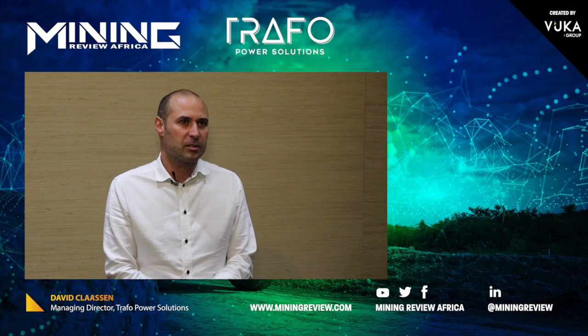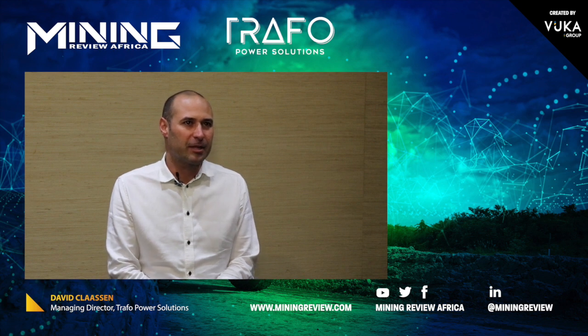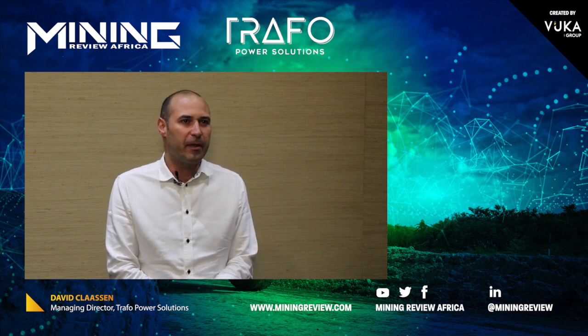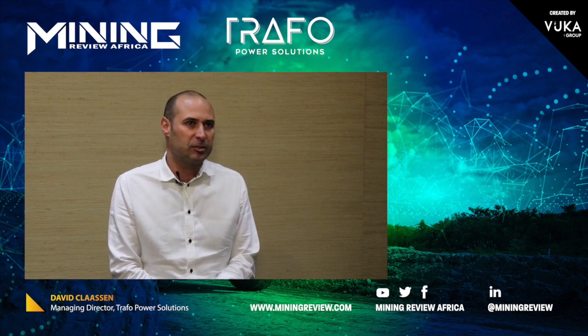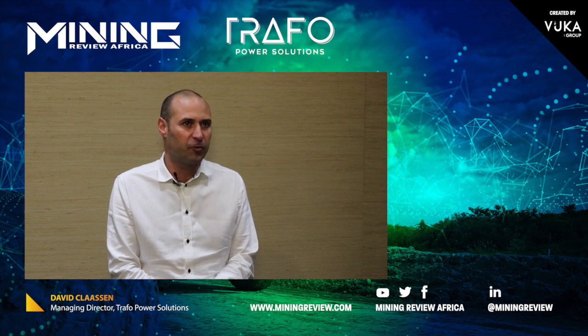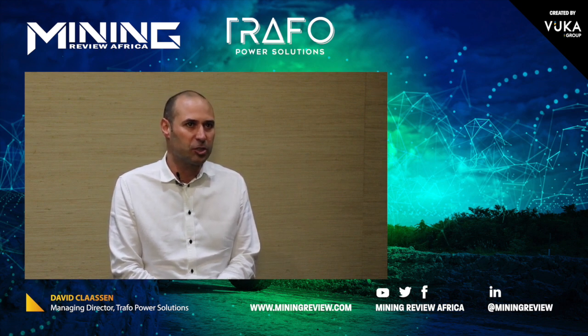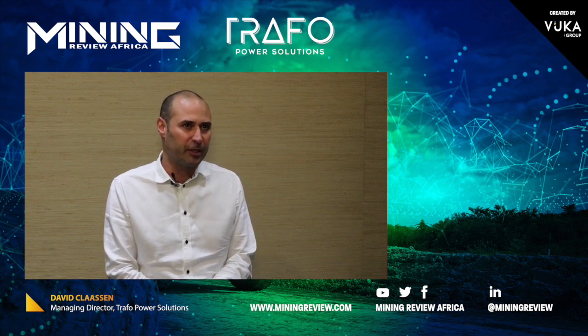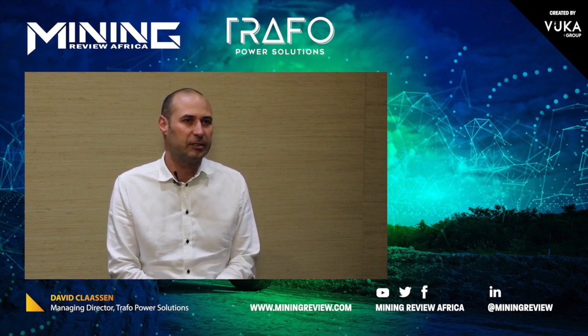Local mining conditions and African conditions are really characterized by high ambient temperatures, and the balance of conditions are similar to anywhere else in the world - very dusty, very wet. From our perspective, we also understand that in the South African context we have power challenges, so one of the major aspects of our design is to ensure the transformer can withstand a volatile power supply. Then thereafter we use all our experience in terms of standard designs for very dusty, harsh conditions, and we design our transformers specifically for the conditions they're going into, and also the enclosure that will house the transformer needs to be specifically designed for that.